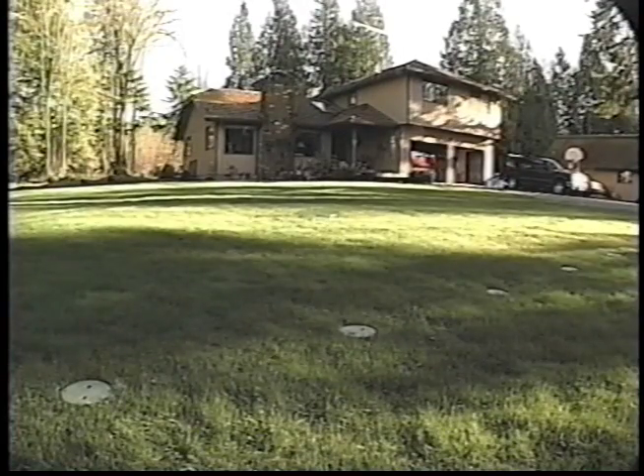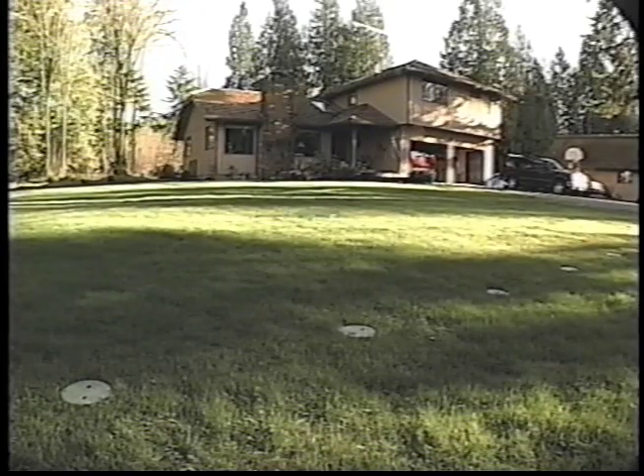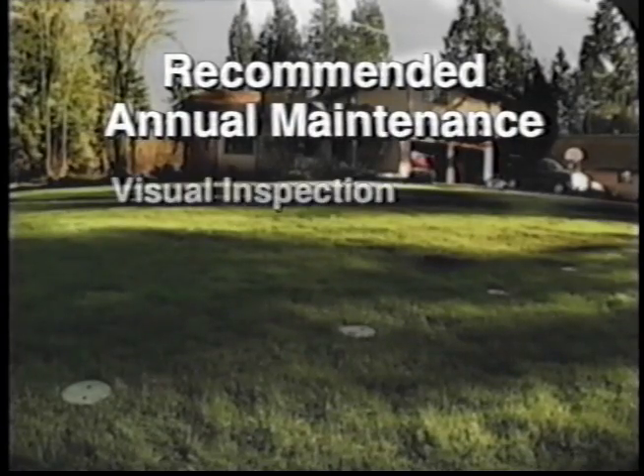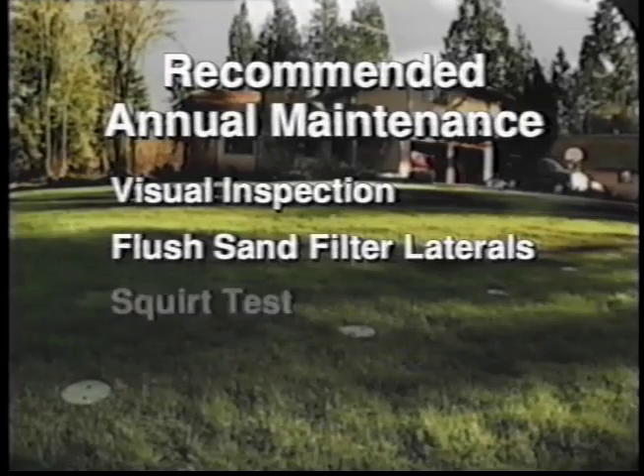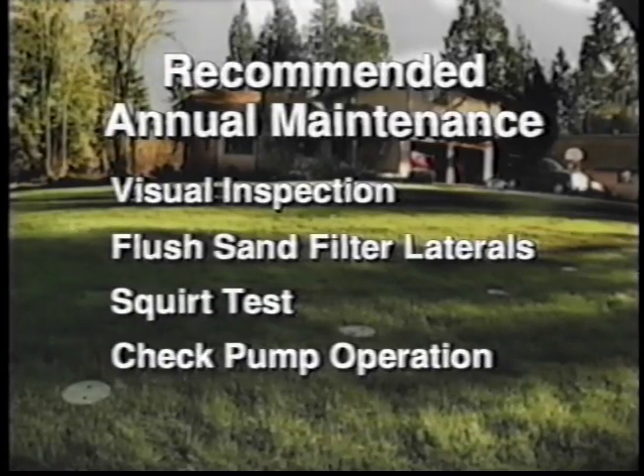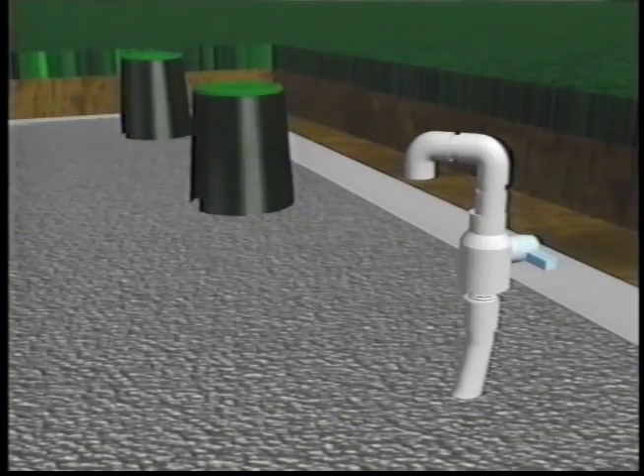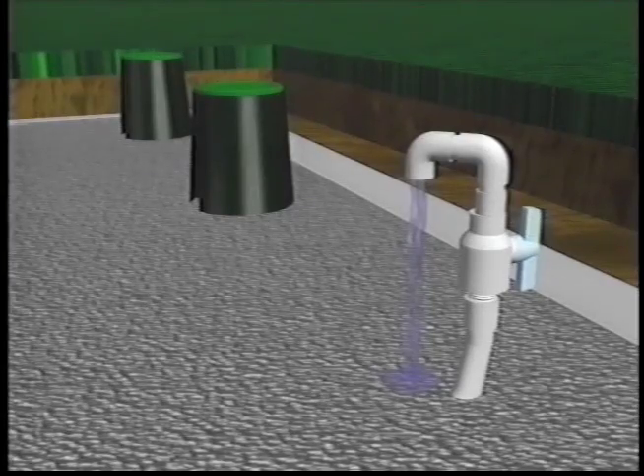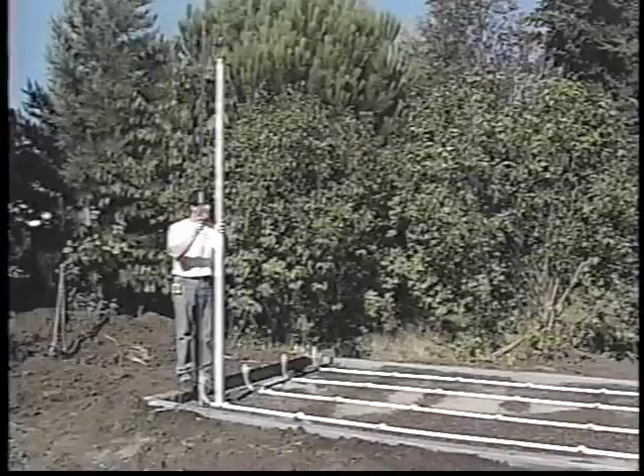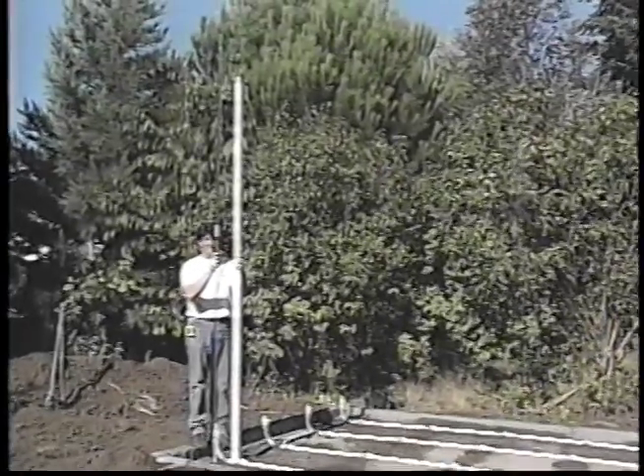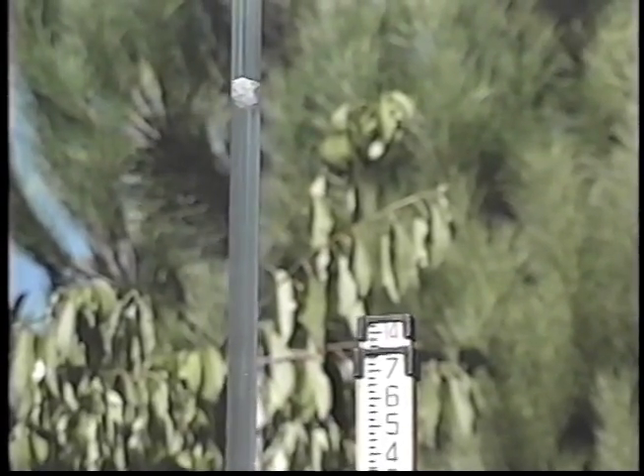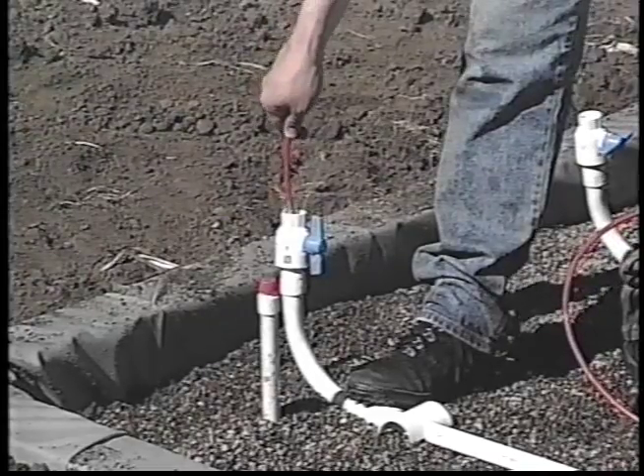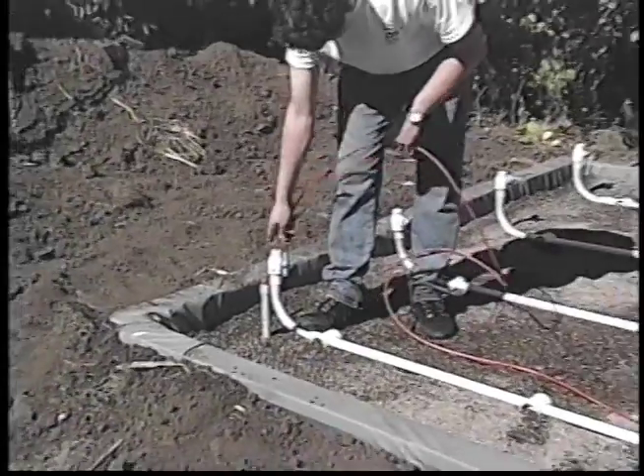The annual maintenance recommended for OSI ISF systems requires only a few tools and normally will take no longer than 30 minutes. Recommended maintenance includes visual inspections, flushing of the sand filter laterals, a squirt test before and after flushing, and verification of proper pump operation. Flushing of the sand filter laterals is performed simply by turning on the pump in the septic tank and then alternately opening and closing the ball valve at the end of each lateral. Using the elbow fittings provided, the effluent is flushed into the clean-out valve box. After lateral flushing, the orifice residual pressure or squirt height is checked using a clear pipe as was done during system installation. If the residual pressure measures higher during the annual inspection than the O&M manual shows during startup, some of the orifices are plugged and lateral cleaning is necessary. Lateral cleaning can be performed with a bottle brush, snake, or a high-pressure jetter hose.